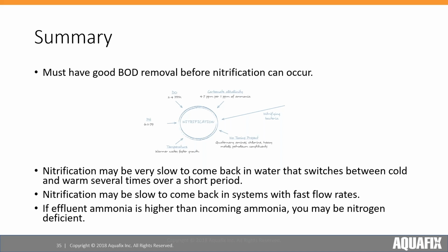It's also difficult to populate nitrifiers when it's due to factors you can't control, so the typical situations will be temperature fluctuations. Mostly this occurs in winter to spring when you go from maybe negative 10 Fahrenheit to another day of 40 degrees Fahrenheit, and then back and forth for several days. Also, washouts may occur at these times with just sudden ice melt and a fast flow rate. In this situation, Vitastim Dynamic Duo can help to repopulate the nitrifiers, but only once the conditions have passed and things have stabilized for at least a few days.